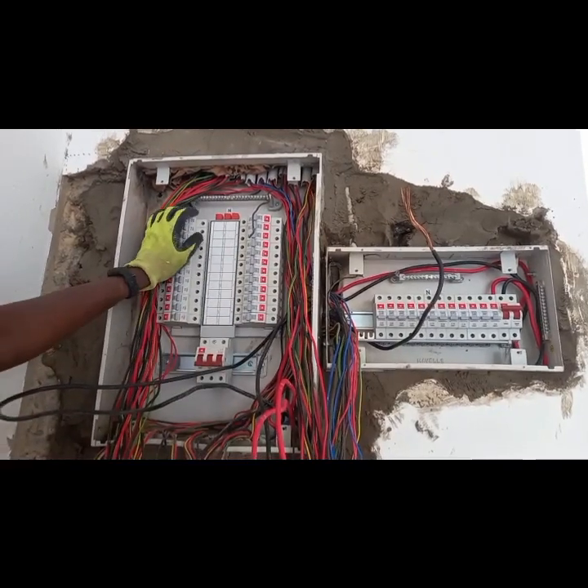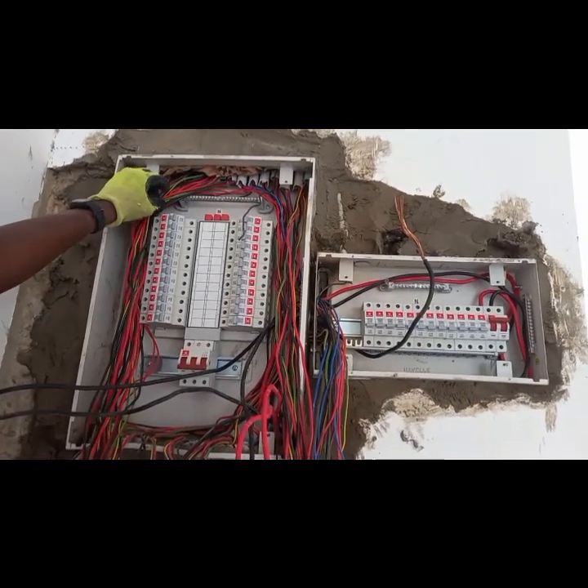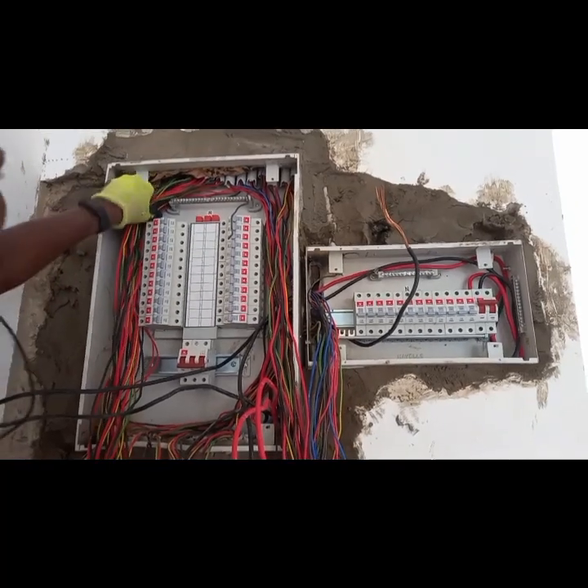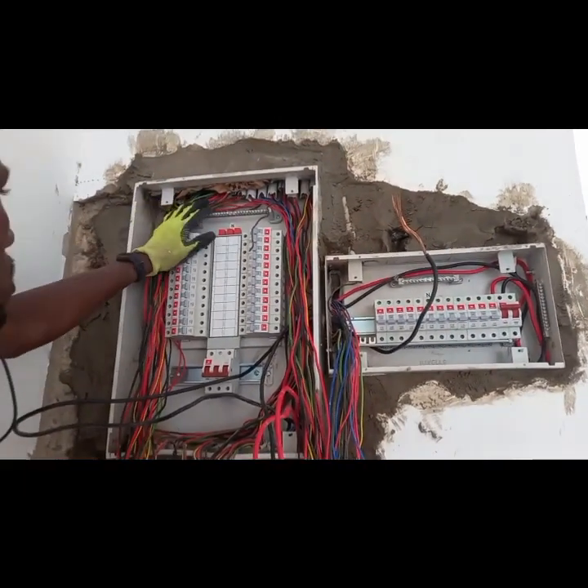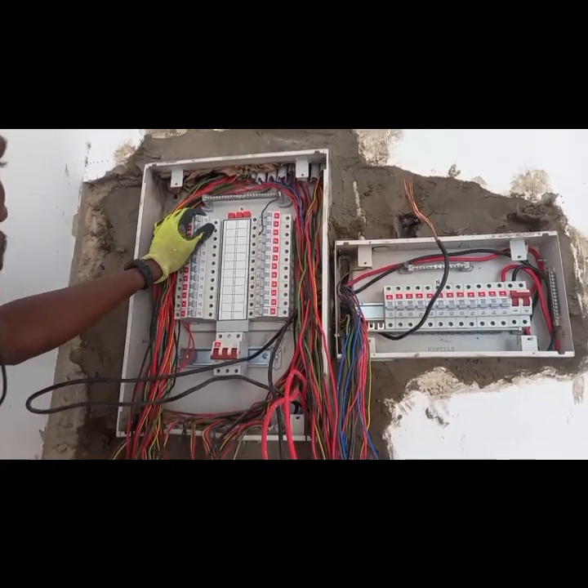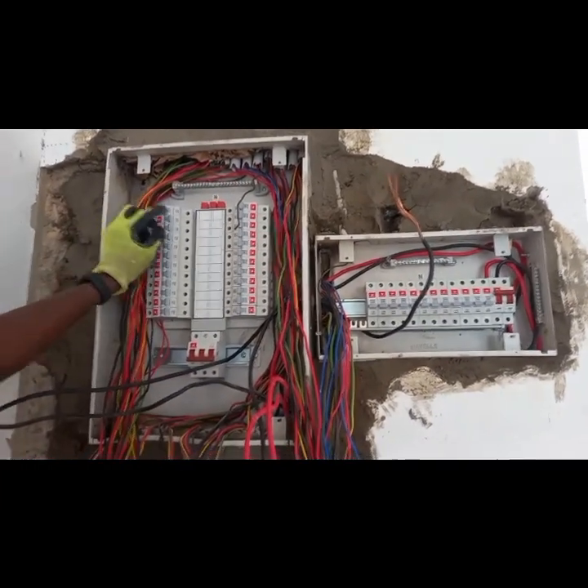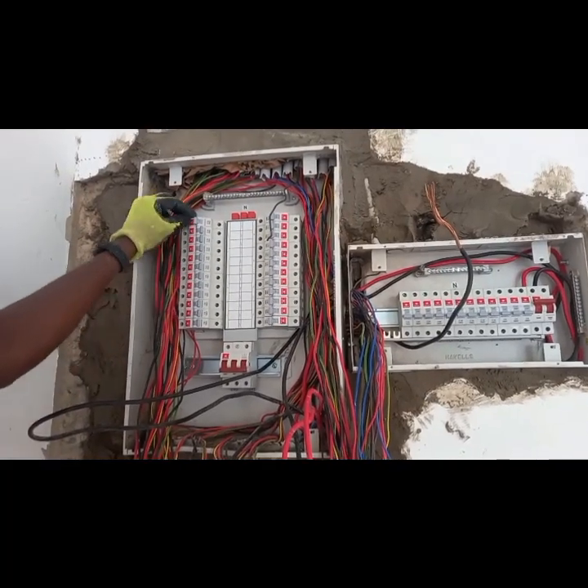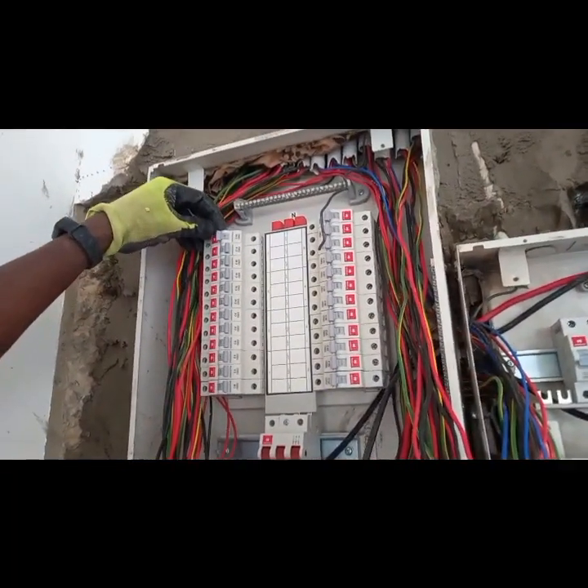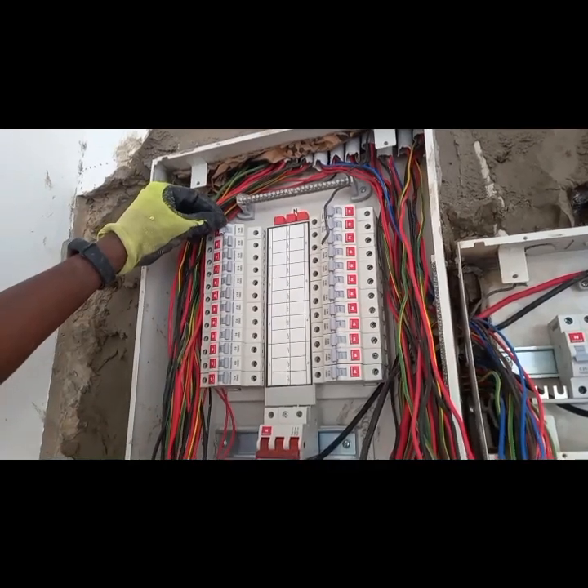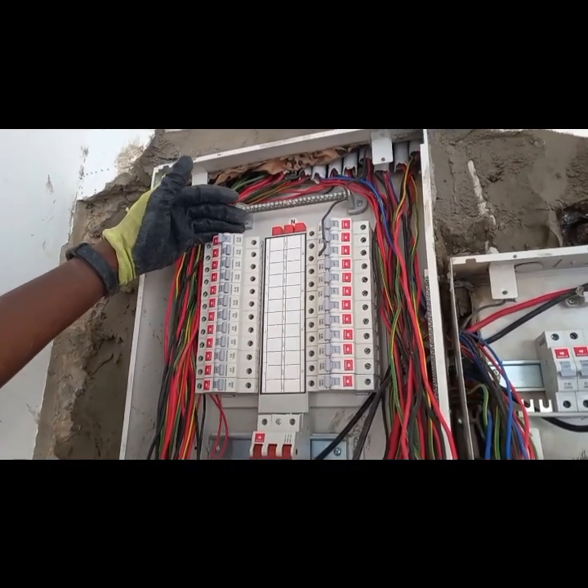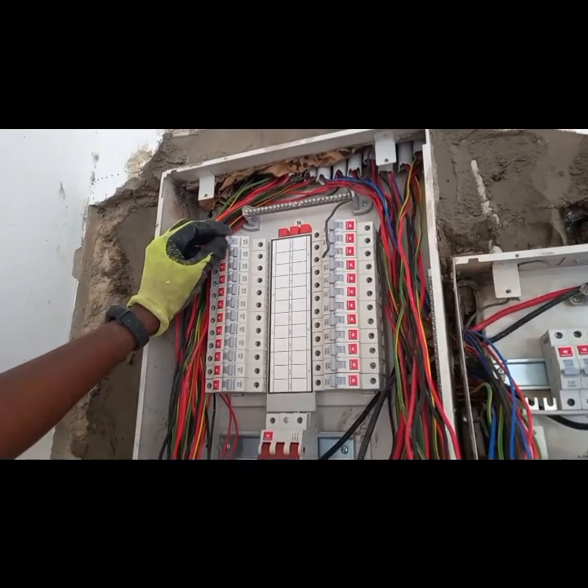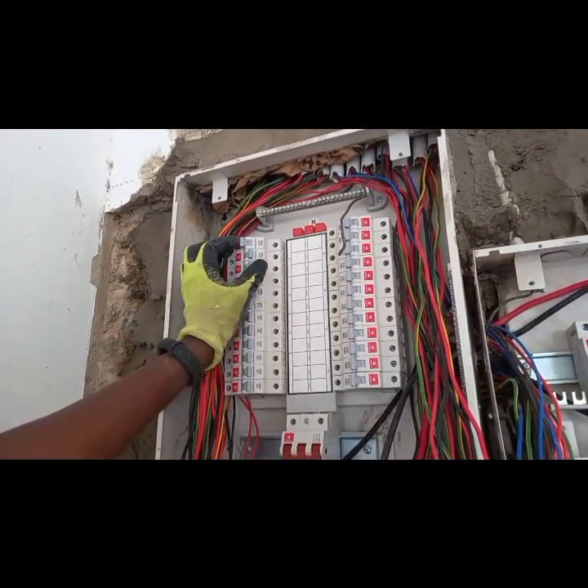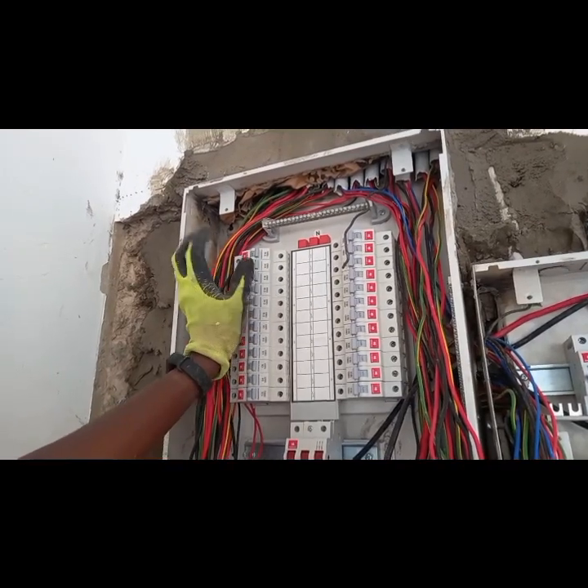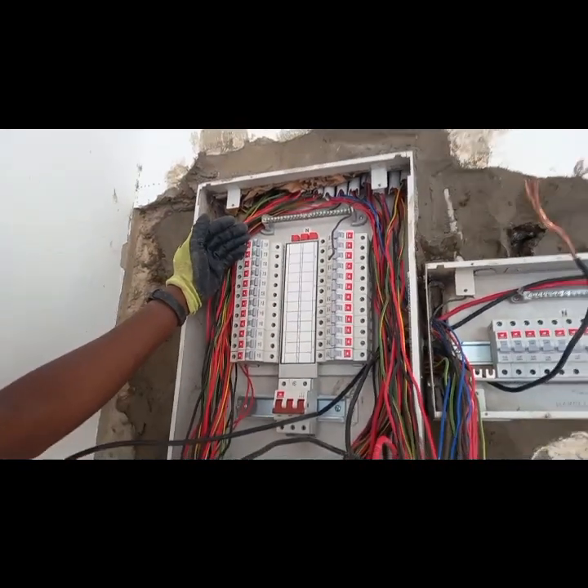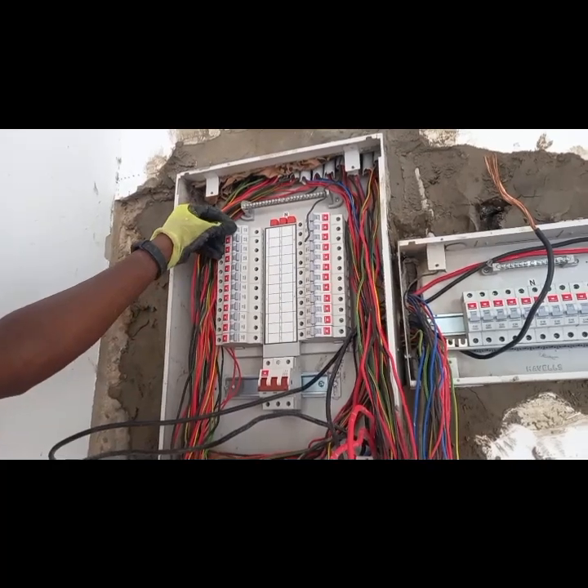So what this does is, let's say an air conditioner circuit has a fault - let's say overcurrent. This MCB has a bimetallic strip inside it. So when it senses a fault, whether overcurrent, overload, or short circuit, the bimetallic strip will heat up, and this will trip. It will go off. So to switch it on again, you have to reset it.